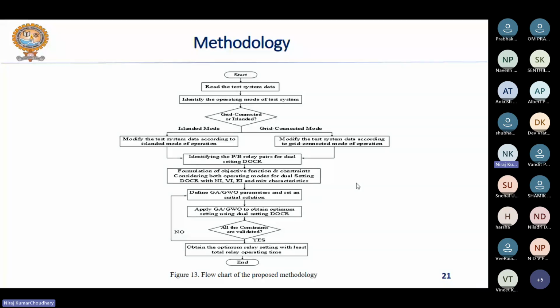That constraint may be your coordination constraint, your constraints related to the operation of the relays, or maybe related to the coordination time interval, or different variables depending upon the type of relay used in the system. And once you have formulated the objective function, then again there is a new area of work. You can use different types of optimization algorithms, hybrid types of optimization algorithms to solve that problem, right? To determine the optimal settings.